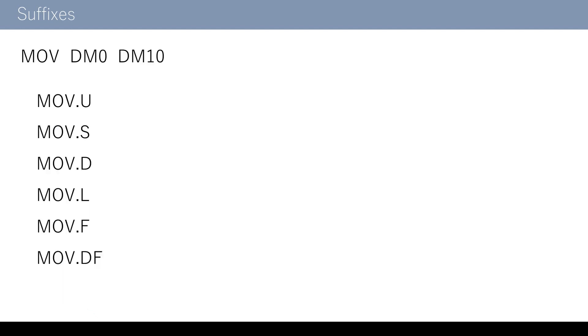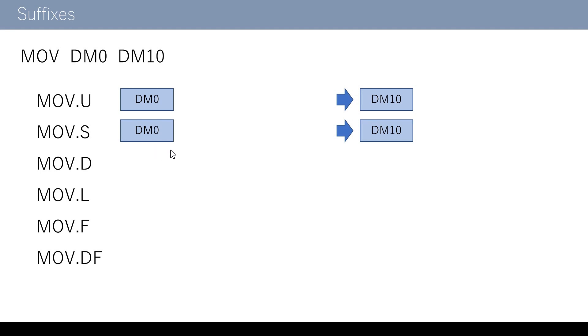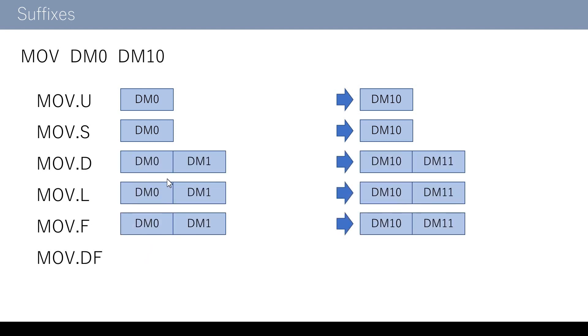Now let me explain about the data size of each suffix using examples of each suffix added to a move instruction — copying the DM0 value to DM10. Move.u and move.s both handle one word, so one word in DM0 is copied to one word in DM10. Move.d, move.l, and move.f are all two-word suffixes — the difference between .d and .l is signed versus unsigned, and .f handles two word single precision floating point. Therefore, two words in DM0 and DM1 are copied to two words of DM10 and DM11.